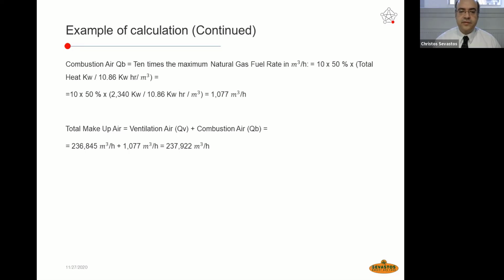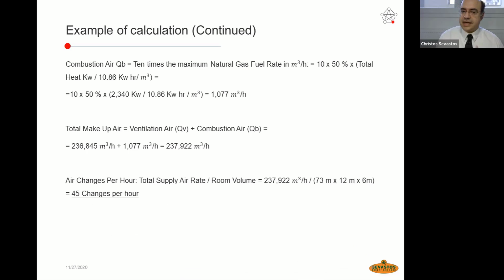This is the calculation of a positive pressure air ventilation system which should be applied. And what can we do with this figure? We have calculated in every detail the air which is provided to the combustion chamber of the ovens, and of course the air ventilation rate in order to extract the heat, to create an air movement inside. With this figure, we can calculate the air changes per hour. Air changes per hour is very simple, the division of the volumetric air by the volume of the room. And this division by the overall room volume gives us the changes per hour. So this is the figure that we have been seeking after all these exhausting calculations.